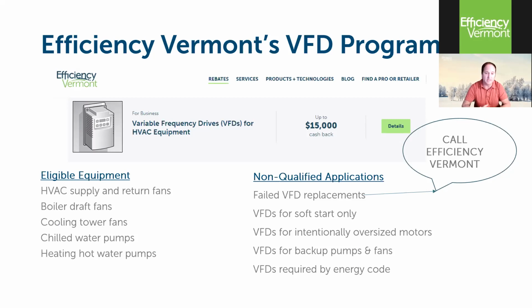The question came up earlier about soft starts. If you're looking to replace a soft start with a drive purely for soft start capability, that's a no-go zone for us. VFDs for intentionally oversized motors, that's kind of a funny one because most HVAC motors are intentionally oversized. They are sized for design days plus 20% or so. So they are by nature bigger than they need to be for 85% of the days in the year. So put a little asterisk next to that one. We may still be able to help there.